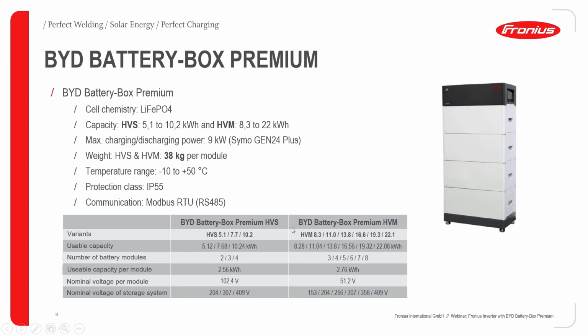Let's look at the HVM, because that's what we're using at the moment. So you go from the 8.3 capacity, which will be 3 modules connected on top of each other, and that goes up to 8 modules with the 22.1. You can see the kilowatt hours of each module is very similar. The main difference you'll notice here, and this is why the power is different later on and why one has a higher power than the other, is the module voltage of the HVS is higher than it is with the HVMs. So that'll have a bearing on the maximum power that you can have with each battery module going forward. But we'll get into that in a bit more detail later.